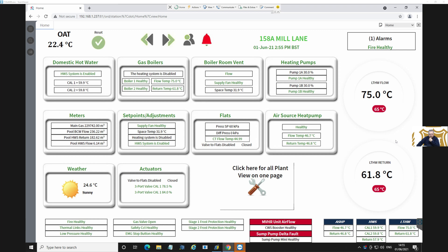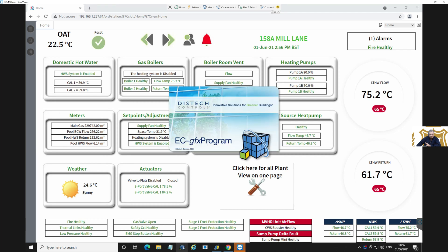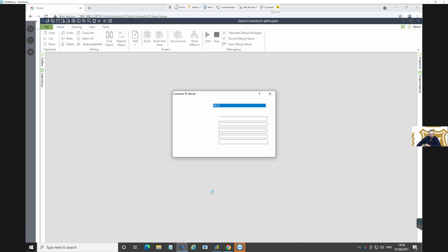They're saying that the display on the MCP1 panel is displaying the domestic water temperatures - 59.9 and 59.8 - differently on the display in the panel compared to what's being displayed here. So I'm going to quickly look and find out why that is, if that is the case. This is the Distech system, so it's using a Distech controller. We're going to load up Distech and connect into the physical controller that's in the panel.